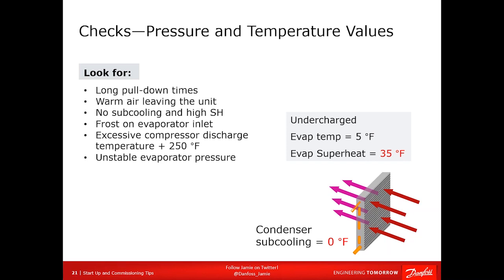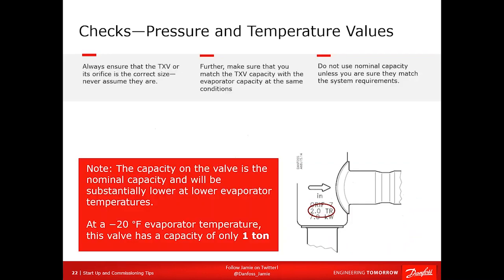Also, if you have flash gas in your liquid line, you're going to have unstable evaporator pressure. Unstable evaporator pressure is a common sign of flash gas at your metering device. So if you have an unstable evaporator, there's a good chance either somebody has reduced your superheat on the TXV to a ridiculously low level, in which case you wouldn't see a 5-degree evaporator temperature and 35 degrees of superheat, or you've got flash gas at the TXV inlet.